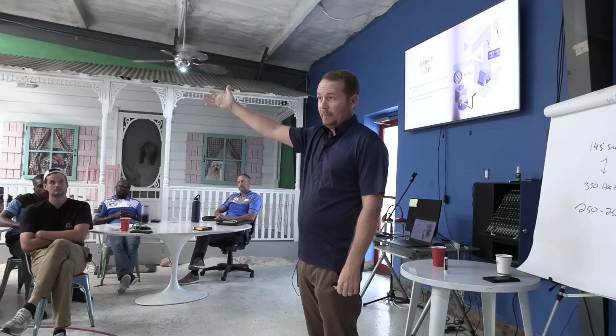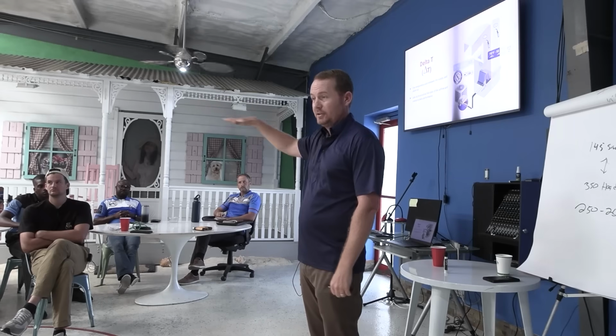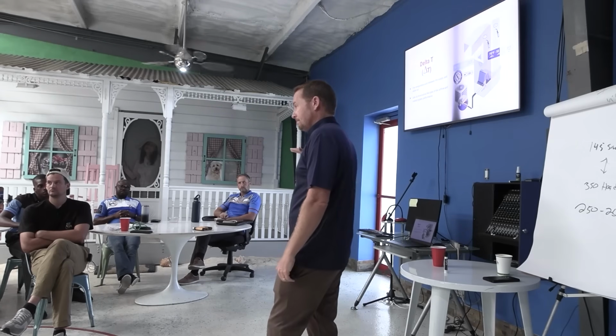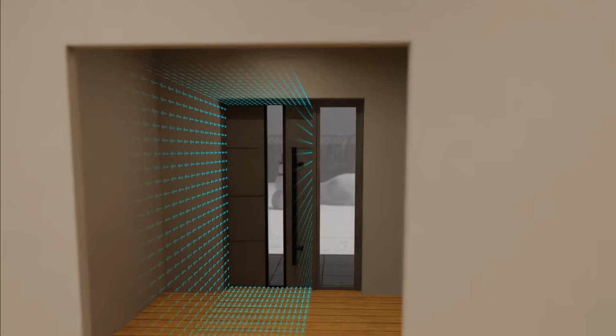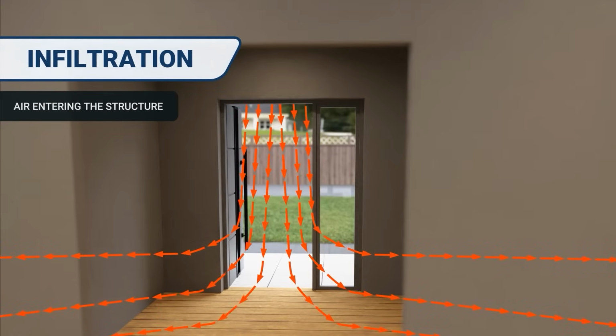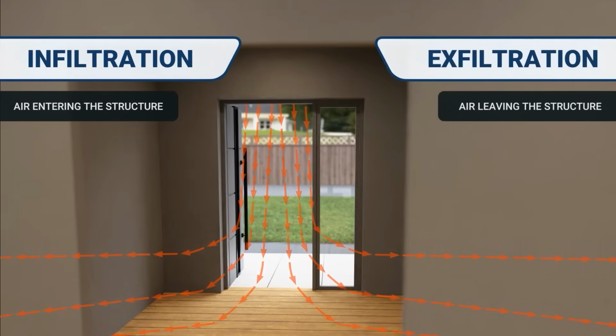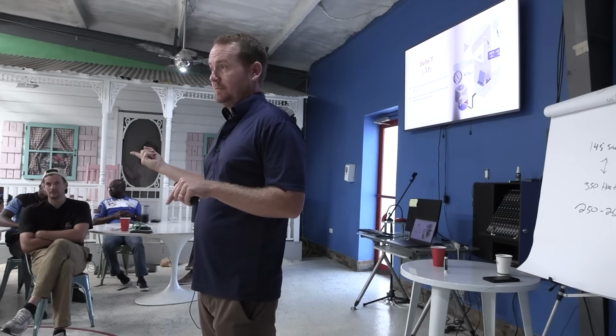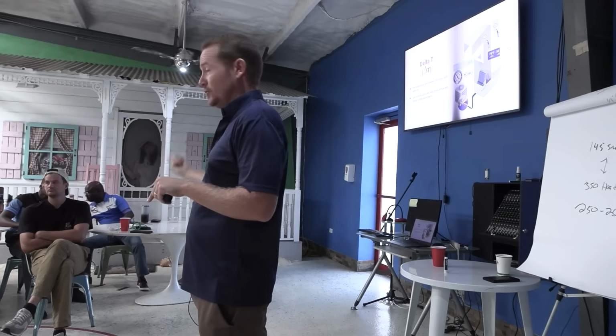Well, now, what happens to the occupied space? What happens to the pressure in the occupied space? It's under negative pressure, because you're losing some of your positive pressure. It's not going back into the space. So now, this whole occupied space is under negative pressure. And if it's in on position, that's happening all the time, right? It never stops being under negative pressure, which makes your moisture problem worse.